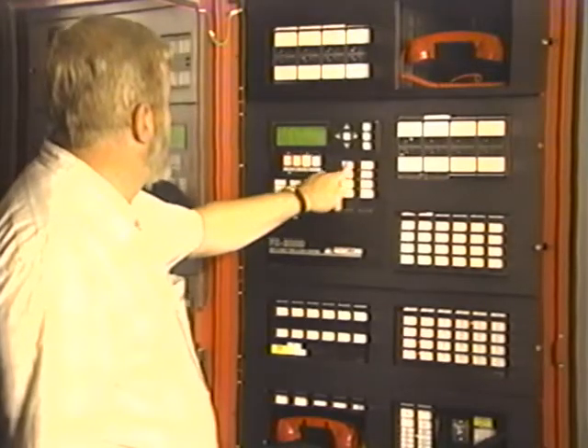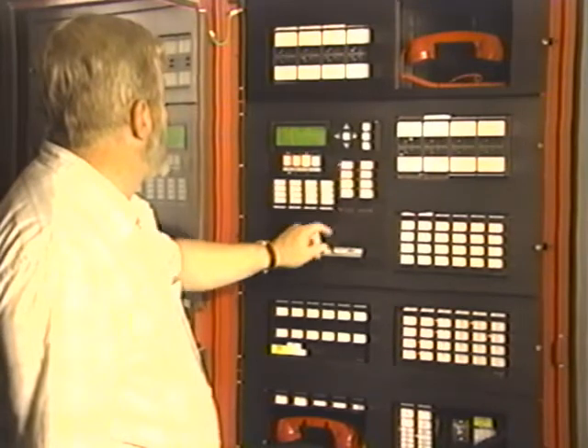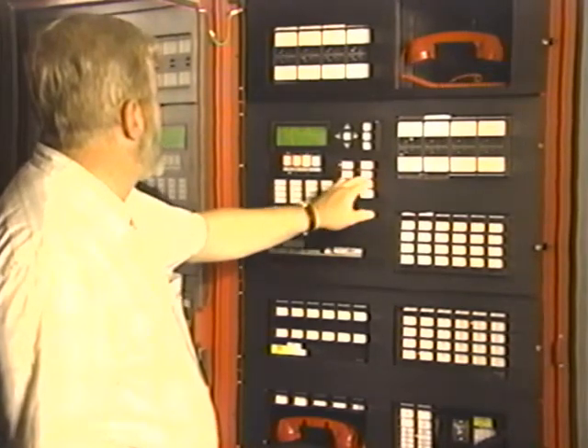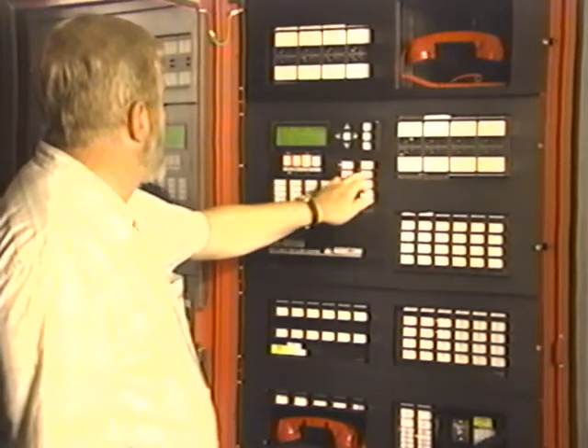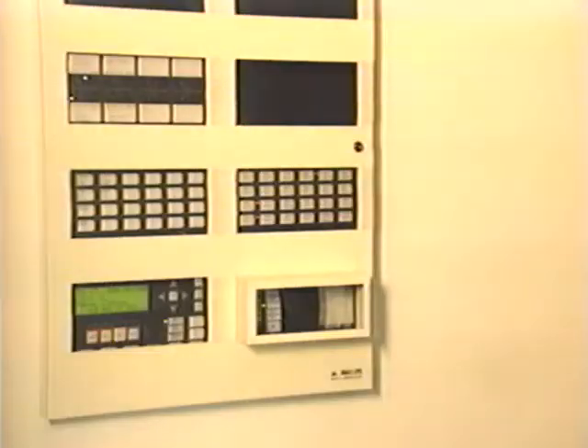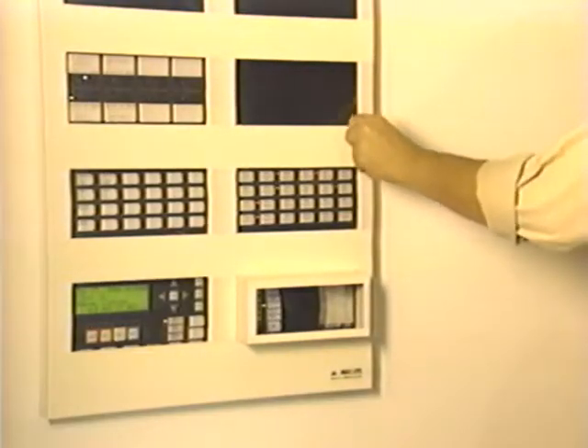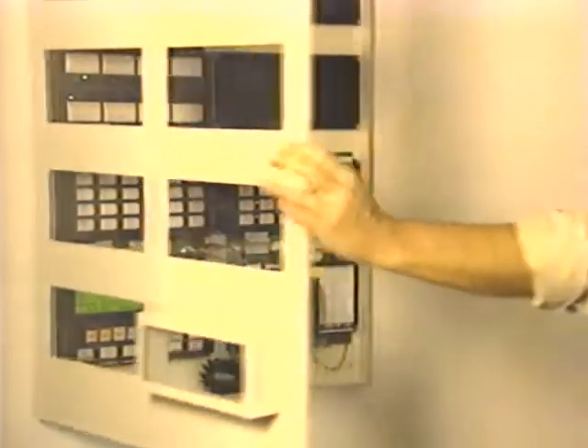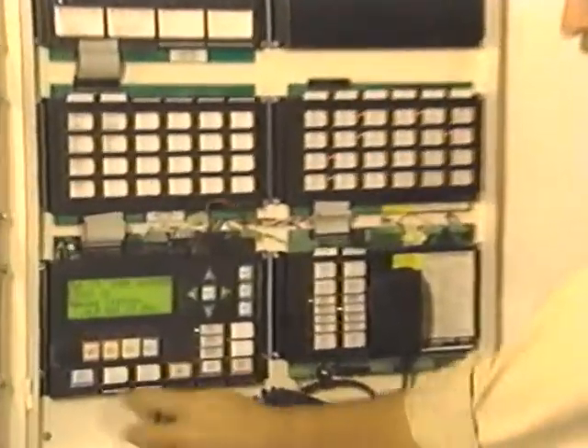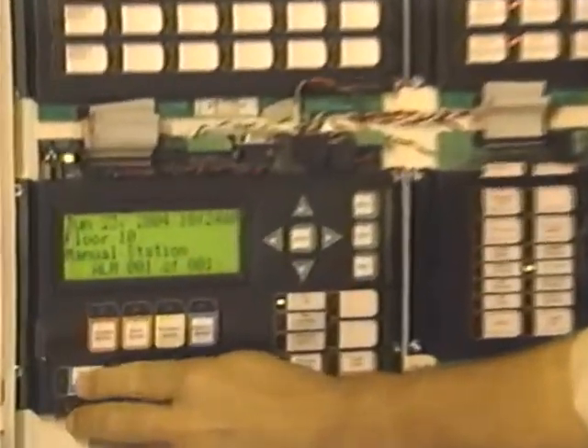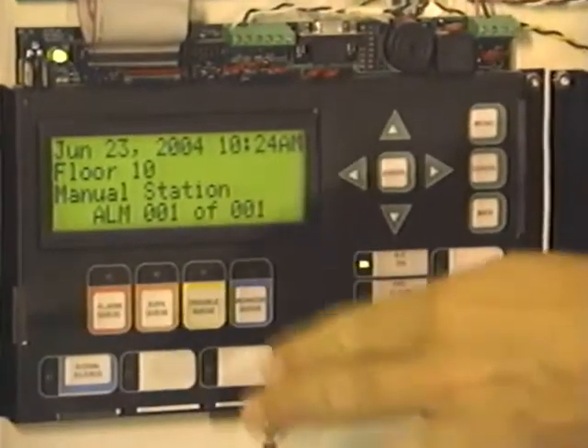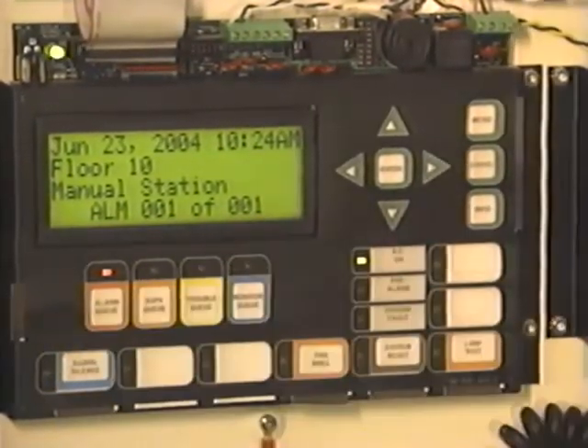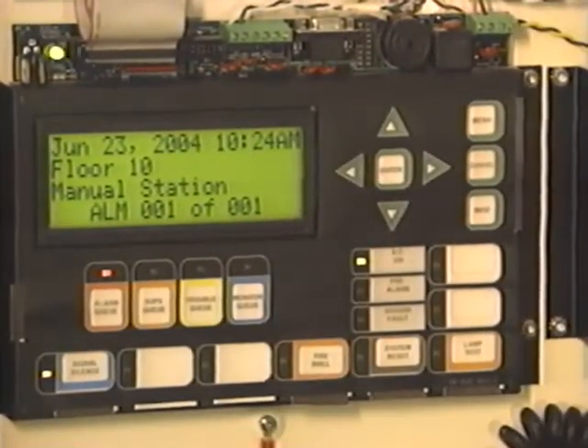Reconnect the secondary power as soon as the primary supply has passed the test. If your system has one or more remote enunciators, they should be functionally tested on an annual basis. Make sure the enunciator screen is functional and readable.